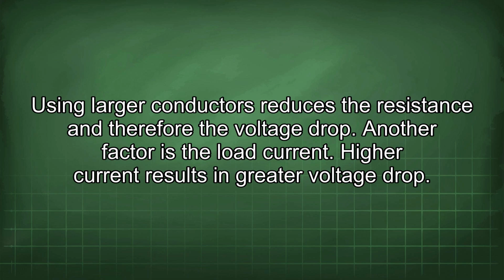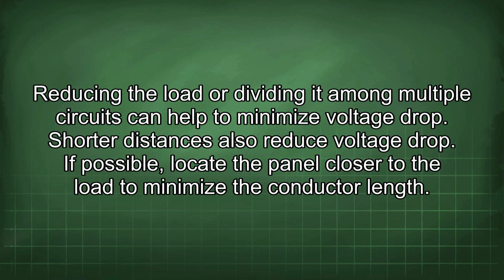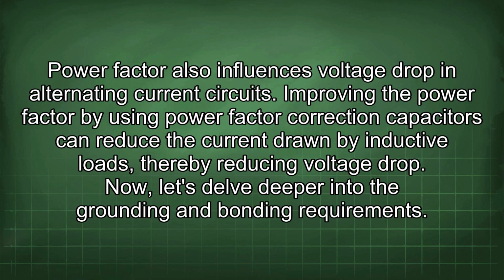Another factor is the load current. Higher current results in greater voltage drop. Reducing the load or dividing it among multiple circuits can help to minimize voltage drop. Shorter distances also reduce voltage drop. If possible, locate the panel closer to the load to minimize the conductor length. Power factor also influences voltage drop in alternating current circuits. Improving the power factor by using power factor correction capacitors can reduce the current drawn by inductive loads, thereby reducing voltage drop.